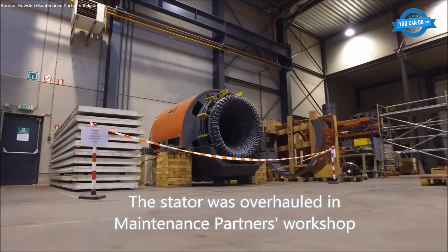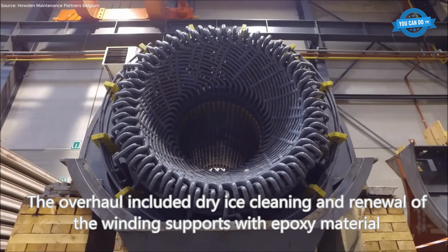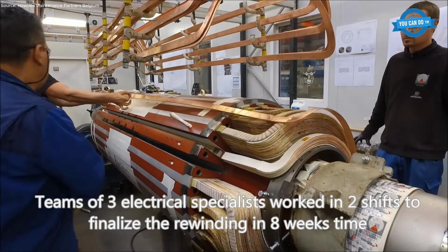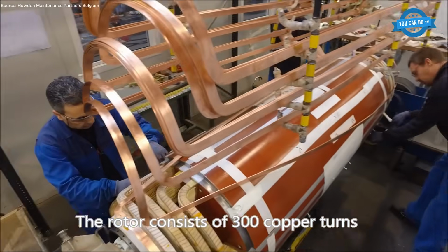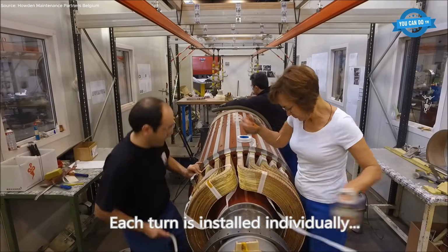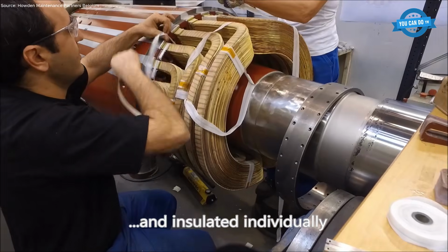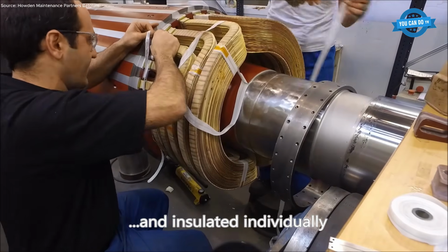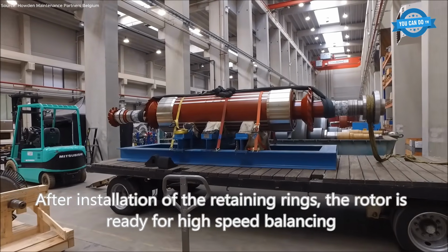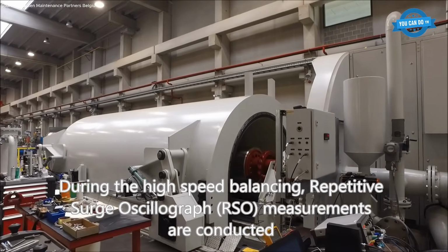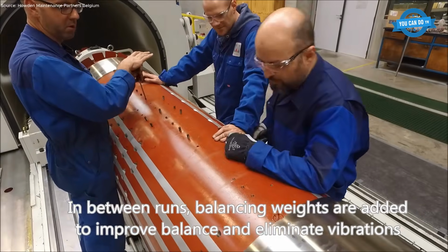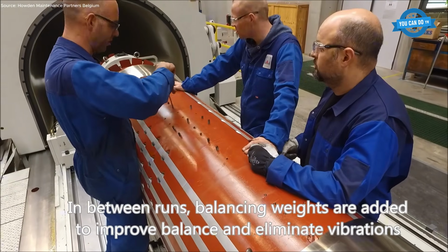Maintenance partners completed the rewinding and high-speed balancing of a 15 MVA generator rotor within 8 weeks. The overhaul included dry ice cleaning, epoxy support renewal, precise rotor rewinding, RSO testing, and dynamic balancing up to 3,600 revolutions per minute, ensuring electrical integrity and operational stability.